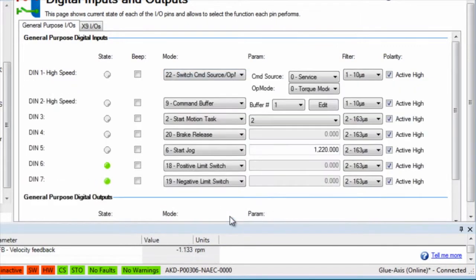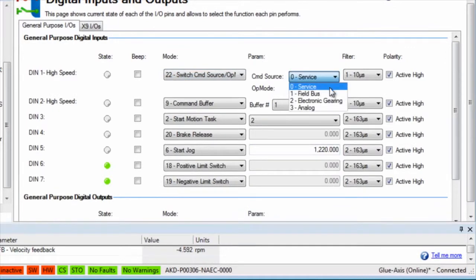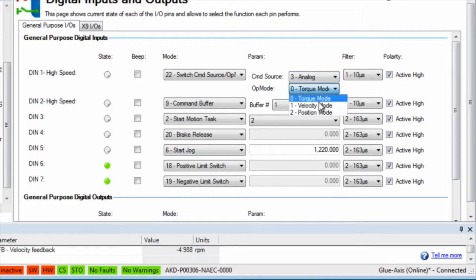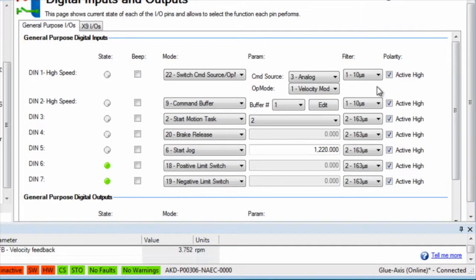Input 1 is set to mode 22, switch command source and op mode. When input 1 goes high, the command source will become analog and the operation mode will become velocity.